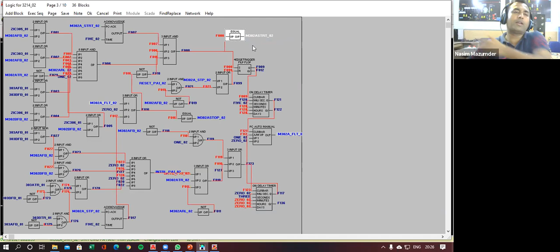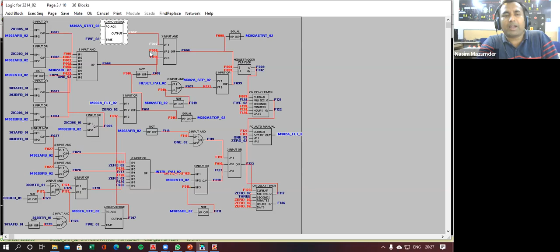Okay. This is your hard tag, which is communicating between your PLC and your field, and this is your soft tag, which is communicating between your SCADA and your PLC, SCADA or HMI, you can say. These are called soft tags. And see here, F007 or F008, these are your temporary tags or flags which are generated. I have generated this F007 here and used it here itself. So this has nothing to do with my input or output. It is just generated within the program and utilized within the program. It has no significance in your input scan and output scan.